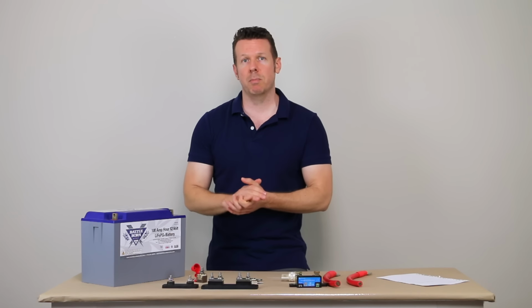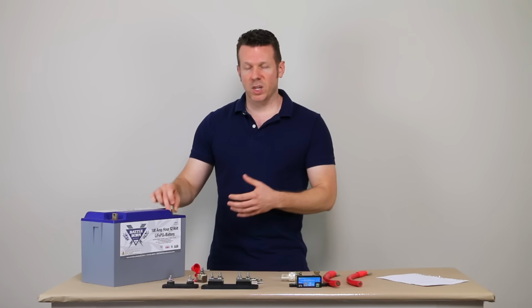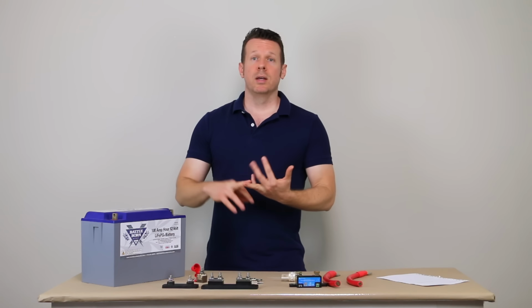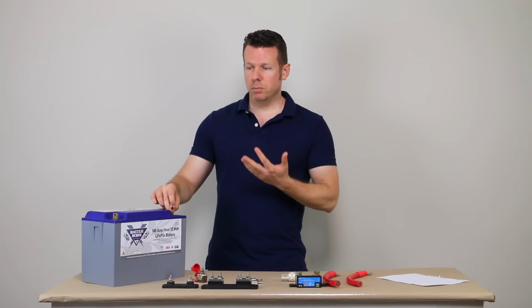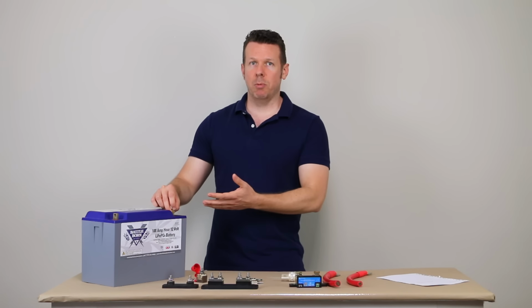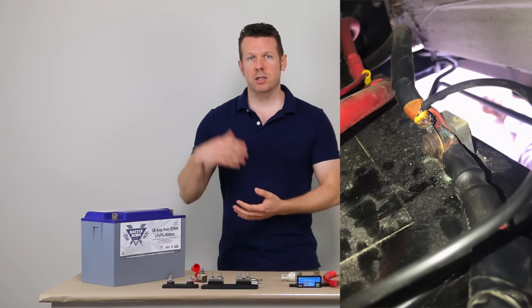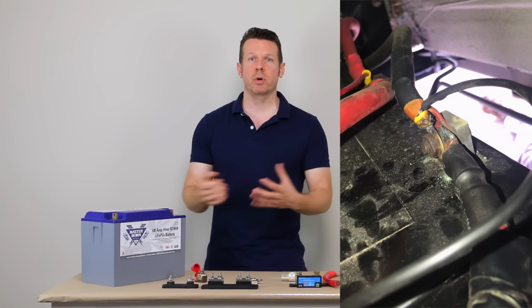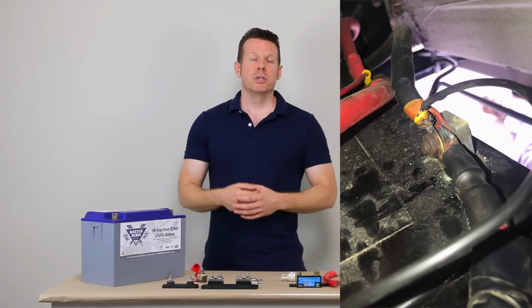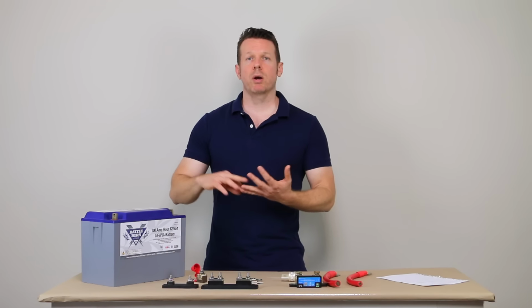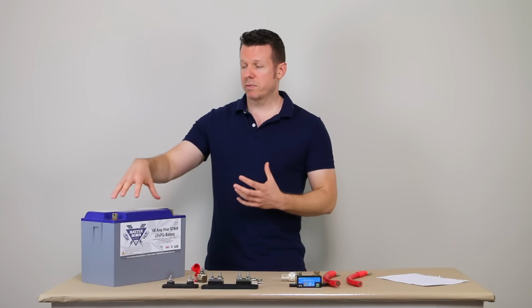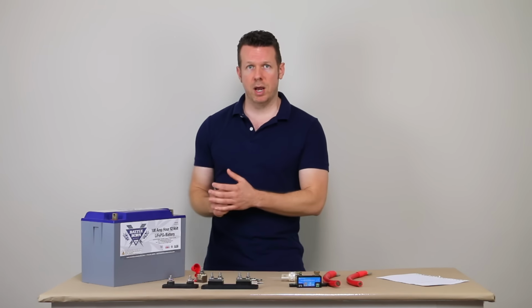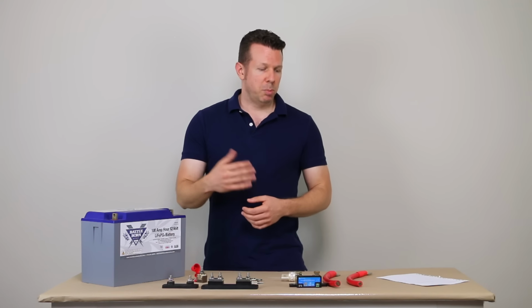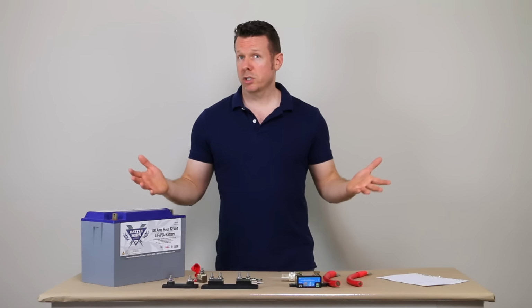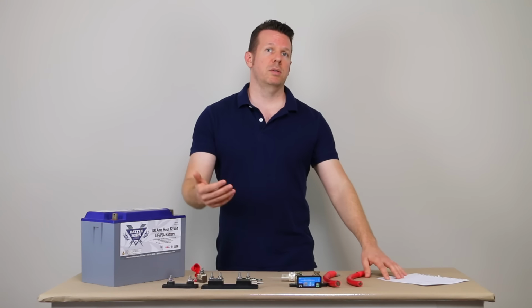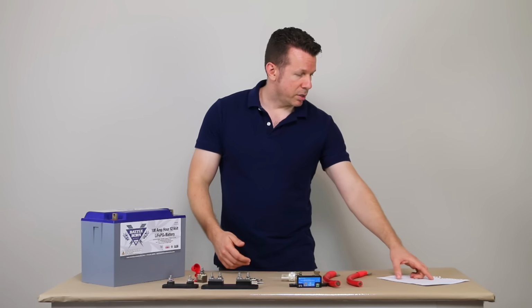It was a human error by the installer, and I would just say have a lock washer or a locking nut. As I said, I could tell by the heat, and when I looked at the terminals, you could see that some of the plastic had melted, and this is a case where things can melt or catch on fire. So check for loose connections. Use the locking hardware. Also, if you have torque specifications from the battery manufacturer, go ahead and torque it down to that torque spec. Loose connections in general can shut down your system mysteriously and also cause things to heat up, melt, or catch on fire. So that is number 6.